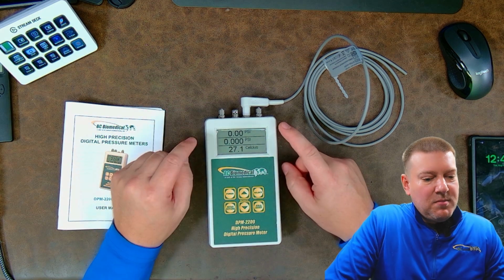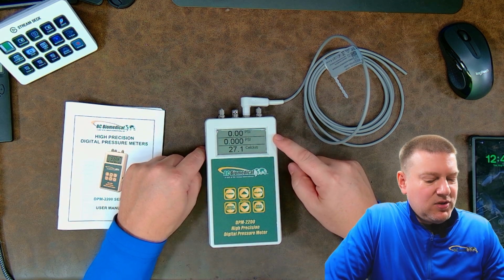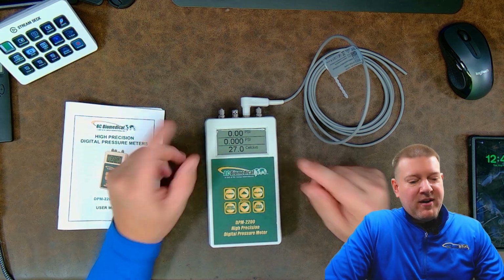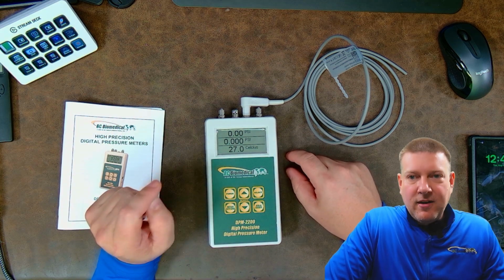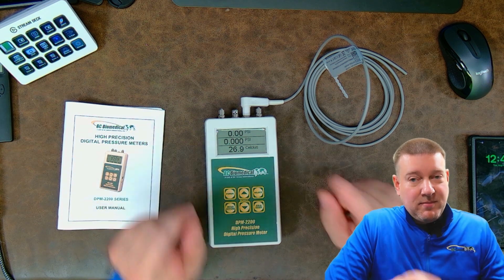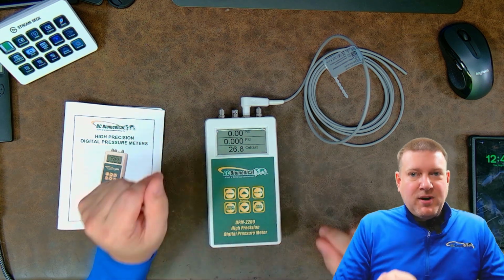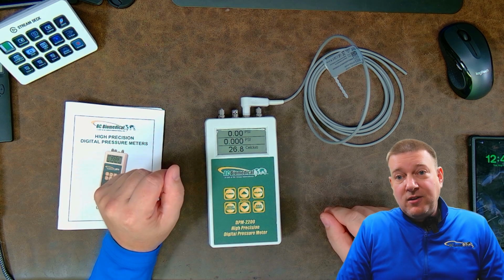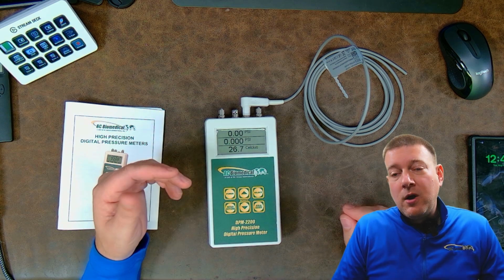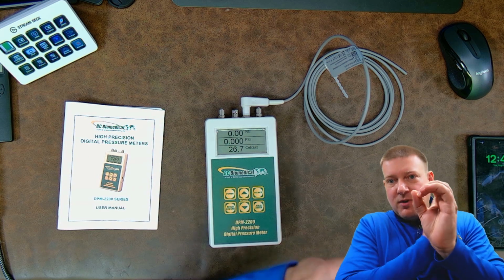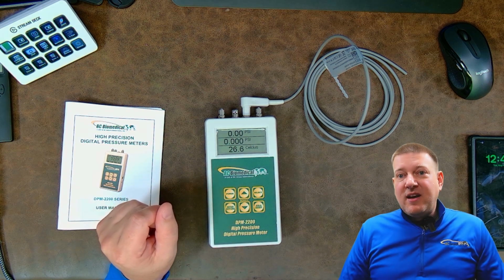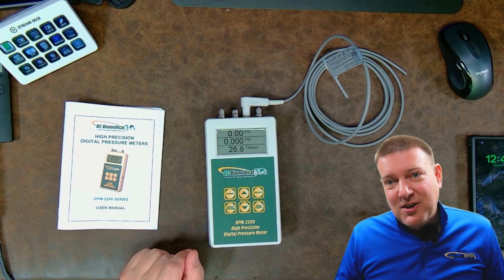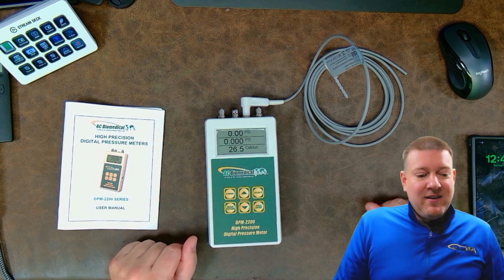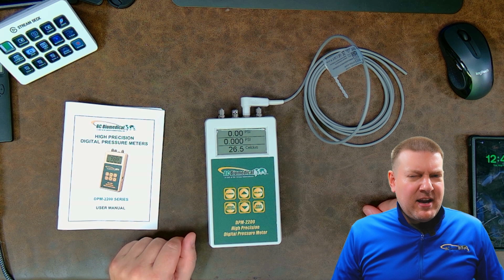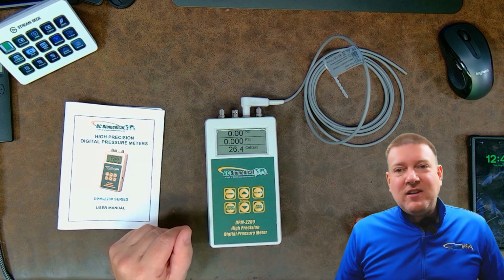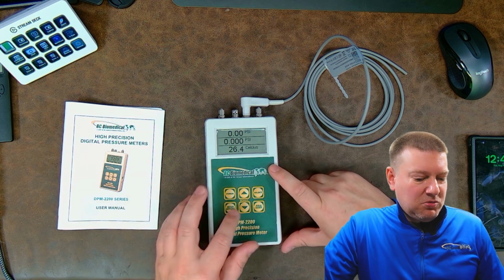So on this screen here, you can see both pressure transducer 1 and pressure transducer 2, along with the temperature. So you have all the numerics right here on the same page. And this can be especially helpful if you're going to do differential pressure, because you can't do that if you don't have 2 different pressure sensors. Differential pressure is something that you'll do if you want to calculate things like flow. You will have some sort of obstruction and you can measure pressure on one side and on the other. And based on the pressure difference and the calculation of the obstruction, whatever it may be, that gives you flow. So if you guys are ever wondering how flow meters work in a lot of anesthesia machines and stuff, that's how they work. But this machine allows you to do those calculations manually if you so choose.